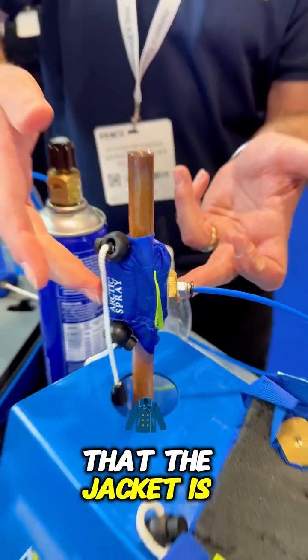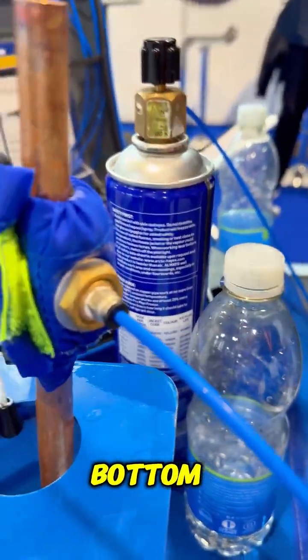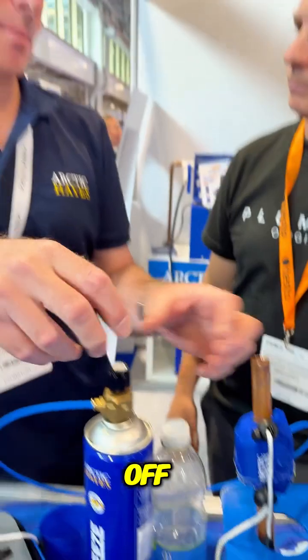The telltale sign is that the jacket's going white and not the liquid coming out of the bottle. A 15mm pipe does probably take a couple of minutes to freeze. When you've not got the noise of the exhibition, you'll hear a clicking sound, which is where the ice plug has then formed. You can then actually turn the aerosol off, because that plug will then form there for probably a good 10-15 minutes, allowing you to do that repair.